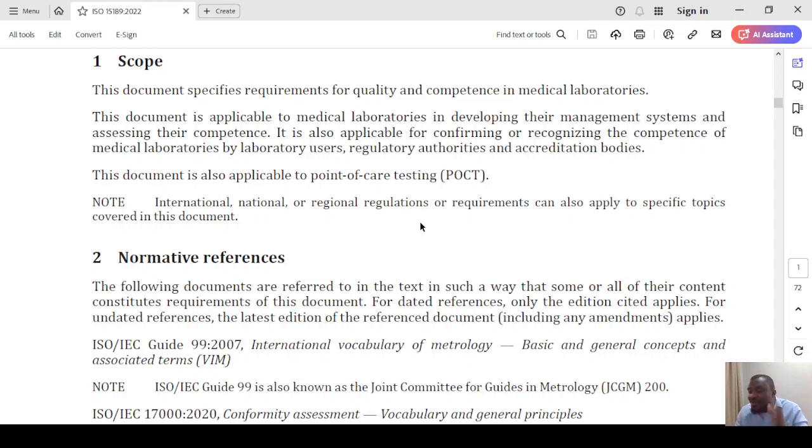So in the lab, if we are required to monitor the temperature, in that place where they are doing the tests, the urinalysis, the HCGs for the mothers, you have to make sure that they have a temperature log that is similar to the one that we have in the main lab. They have to have the thermometers, they have to have the storage conditions that are required in the main lab. Everything has to be translated to those other sites.